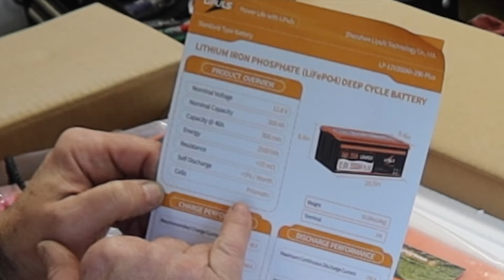So recommended charge current 40 amps, which is really good. My RV has a lithium setting on the converter, and I want to say it says 50 amps. Maximum charge current 200 amps, so obviously it can take it. Recommended charge voltage would be 14.6 volts. And then the BMS charge cutoff voltage is less than 14.6 volts, 3.65 volts per cell. Maximum batteries in connection, 4P4S. So 4 parallel and 4 series is what that stands for. Parallel meaning that you would get the same voltage and increase your current, and series would mean that you would keep your current the same and you would increase your voltage.